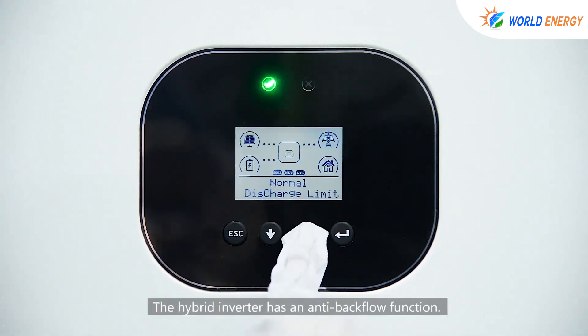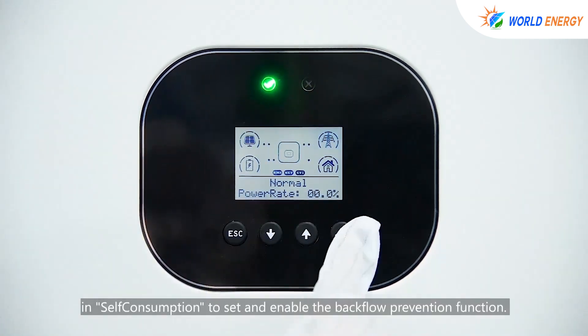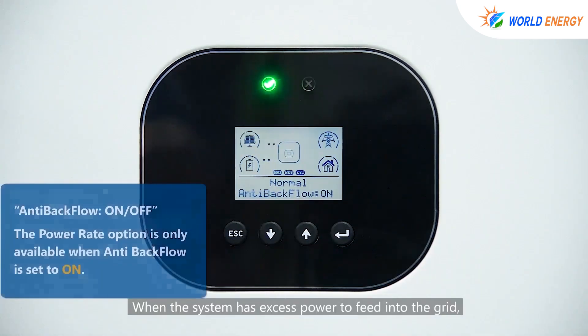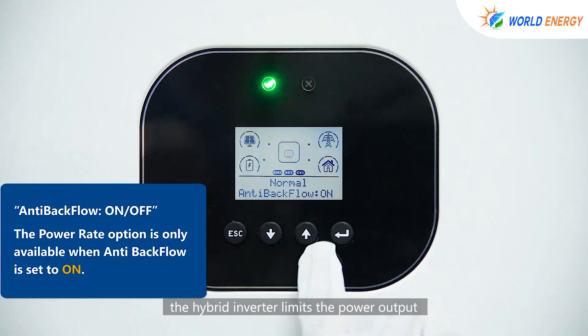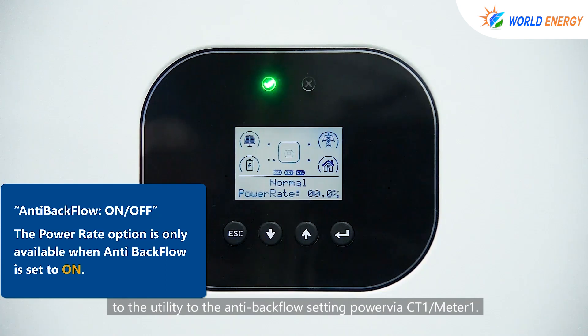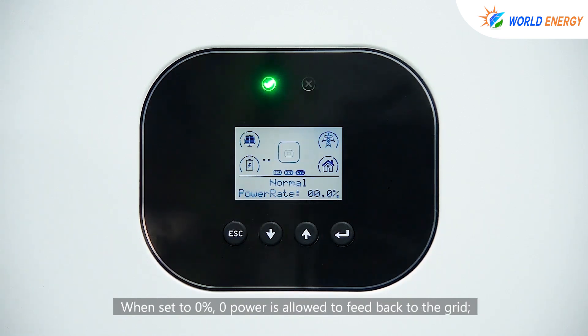The hybrid inverter has an anti-backflow function. Users can press the up or down and enter buttons to enter the prevent backflow screen in self-consumption to set and enable the backflow prevention function. When the system has excess power to feed into the grid, the hybrid inverter limits the power output to the utility to the anti-backflow setting power via CT1/Meter1. The Power Rate option is only available when Anti BackFlow is set to ON. When set to 0%, no power is allowed to feed back to the grid; when set to 50%, 50% of the inverter's rated power is allowed to feed to the grid.